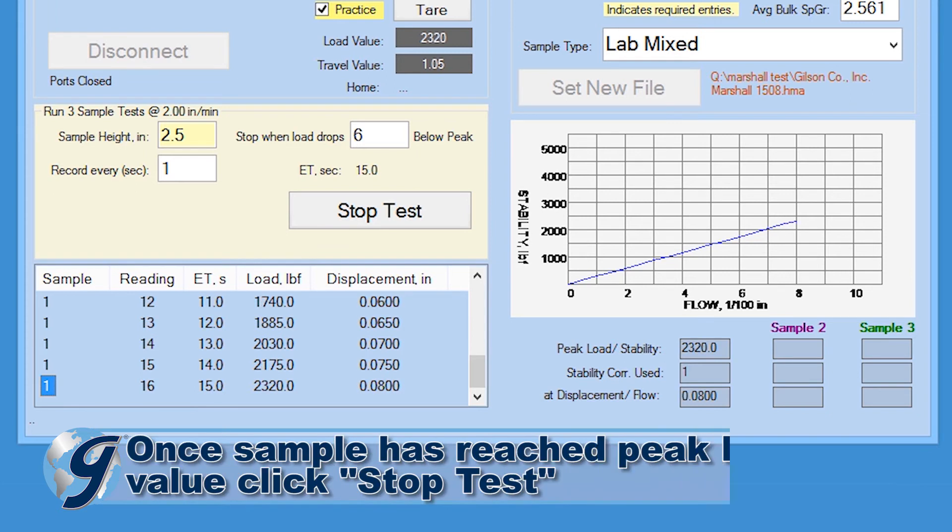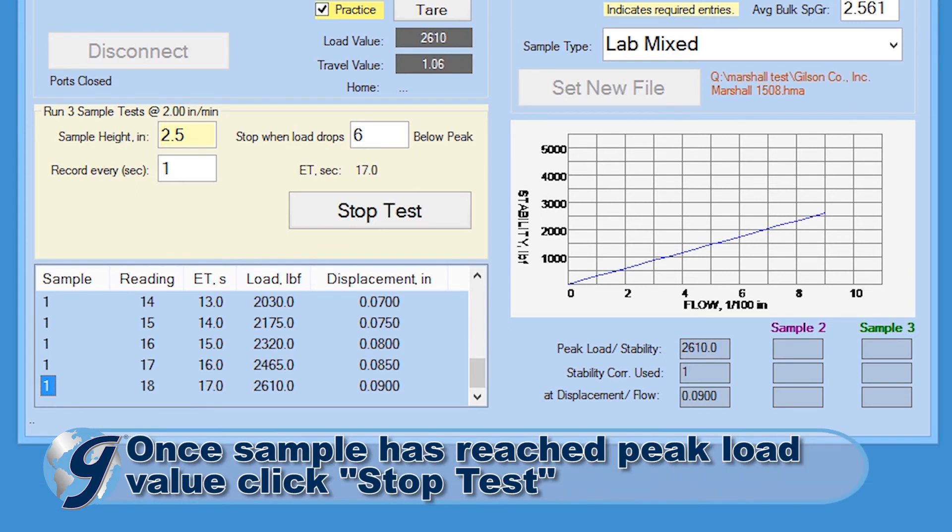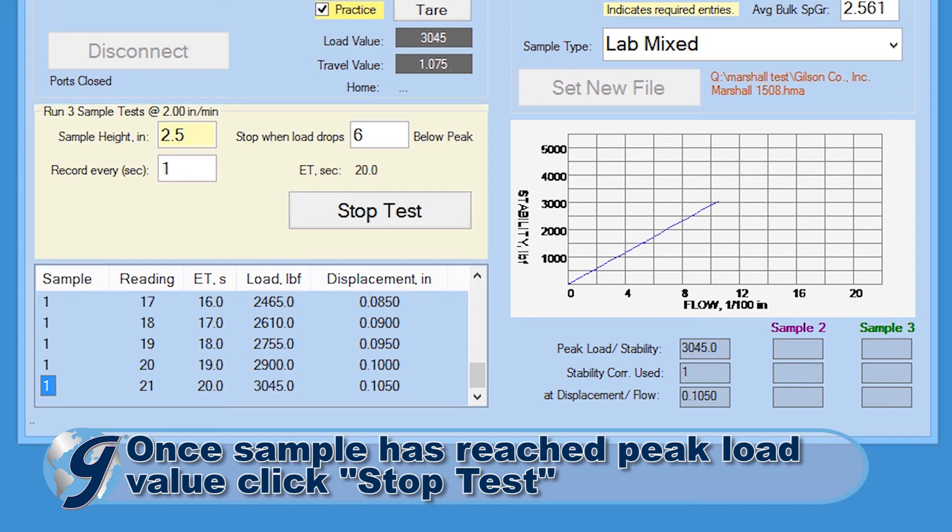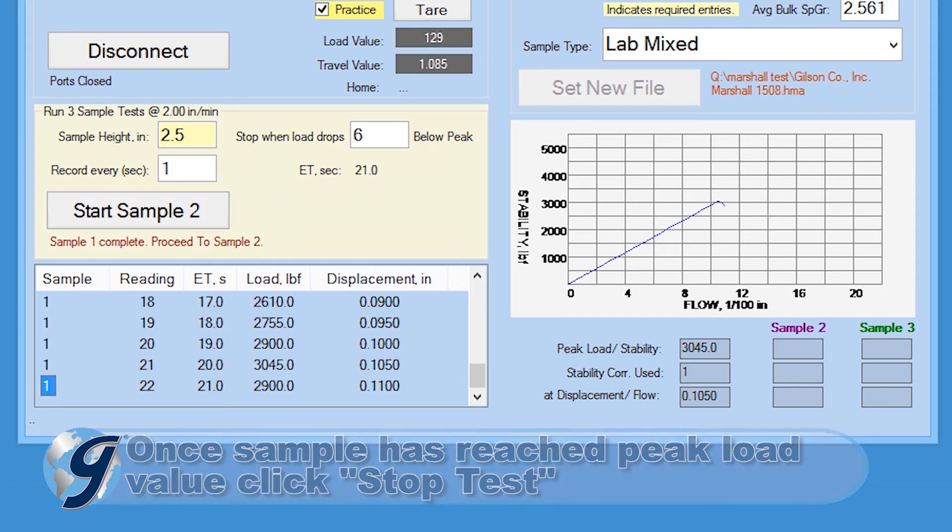Once the first sample has reached its peak load value, click stop test and the data will stop being recorded. If a load drop value was entered in the stop when load drops below peak field during the test setup, the data will stop being recorded at the specified load. Next, lower the platen by clicking on the down button on the load frame. Now remove the first sample.